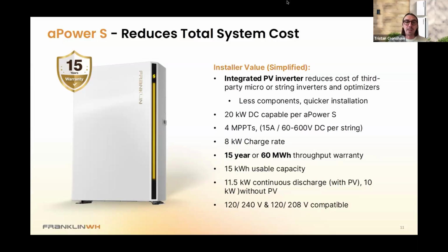So one thing that is unique about Franklin's batteries is we actually maintain a small reserve capacity for a black start capability, which means the battery is actually slightly larger than 15 kWh, but the customer will have access to that full 15 kWh. So we call it the usable capacity. We have about 1.1 kWh that is reserved. That means if the homeowner were to drain the battery to zero in an off-grid situation, there is a reserve capacity to turn on any external PV inverters and basically jumpstart the system the next day without bricking the battery.